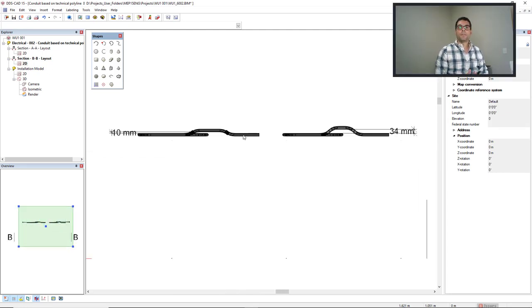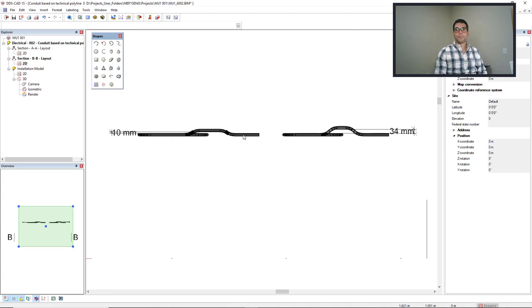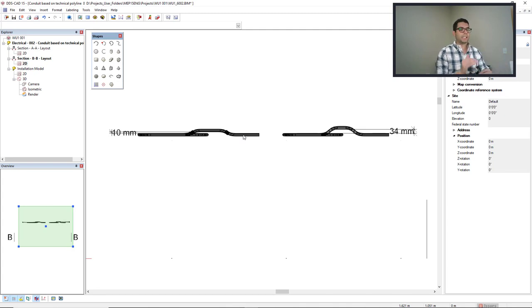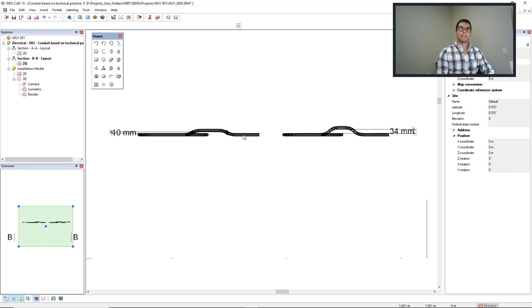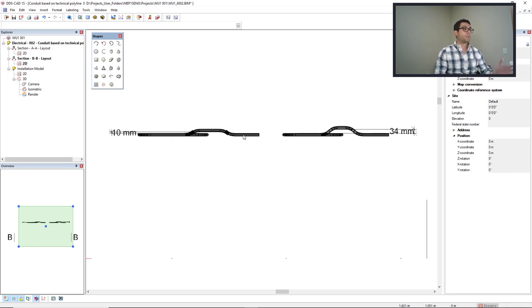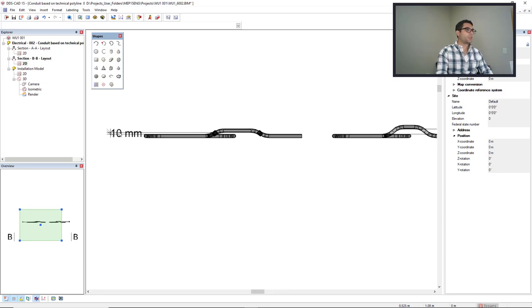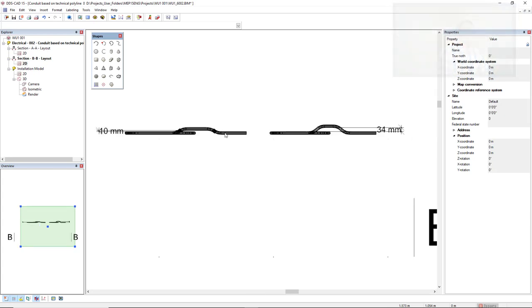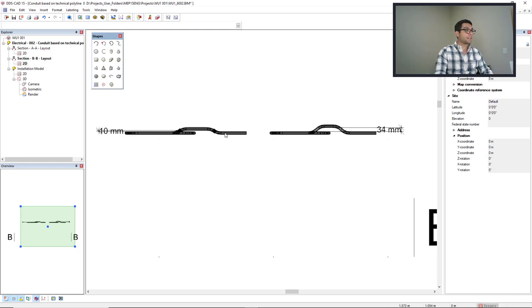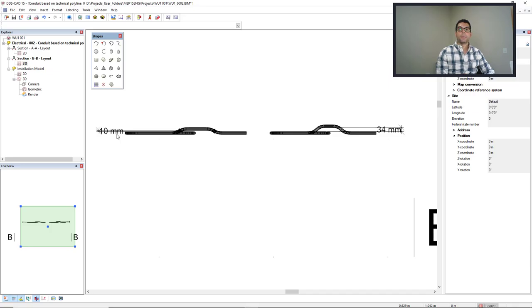So the result is, when we use the function climb over or under the clash to automatically insert this offset, the DDS-CAD will insert the minimal space required so that the bends are not overlapping. But if you do it manually, you can insert whatever you'd like for the offset, but the bends will be overlapping. If you'd like to have the same offset for this conduit size, 10mm of course, you would have to change the bend radius.